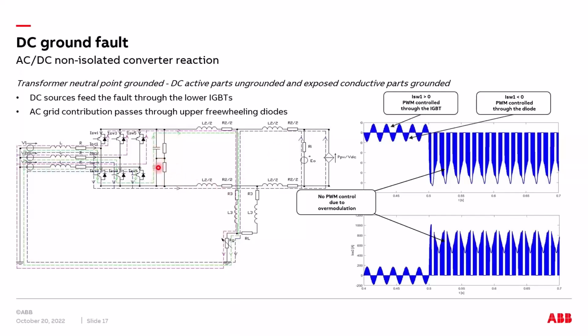The contribution coming from the DC capacitor discharge current passing through the lower IGBTs installed in our converter; the batteries contribution and photovoltaic contribution coming from all the other batteries installed in parallel at that moment, still passing through the lower IGBTs; and we still have the contribution coming from the AC grid, but passing through the upper freewheeling diodes. Here, without considering the so-called IGBTs internal and embedded protection.